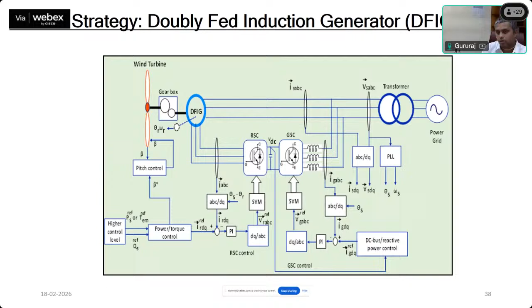And for power quality, the grid side converters and the rotor side converters can be embedded with active filter capabilities, so that if there is a nonlinear load connected at the point of common coupling, the harmonics can be mitigated and reactive power compensation can also be done. And then there is the voltage control of the network. For example, if you have a double fed induction machine working together with other voltage compensating devices like on-load tap changing transformers, D-STATCOMs, and capacitor switching banks, how do you manage all of them to optimize the system components, and thereby improve the voltage profile of the network? And the cost-effective hybrid system architecture is also a very important topic.